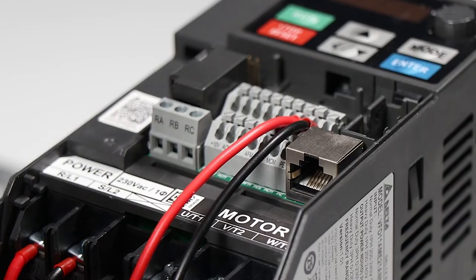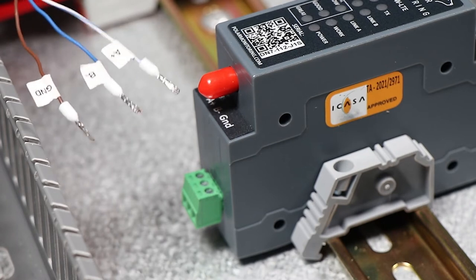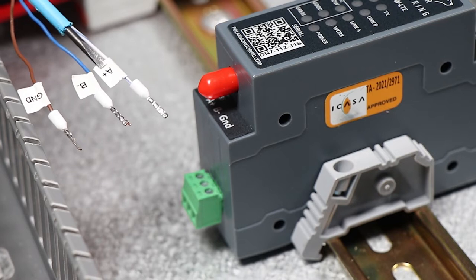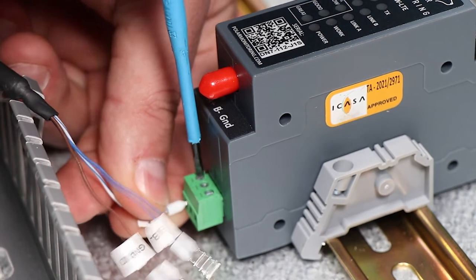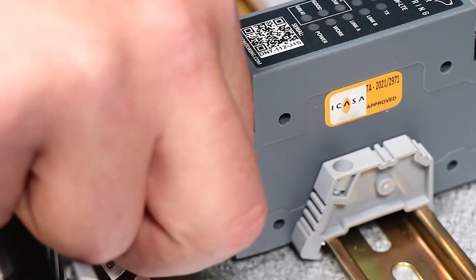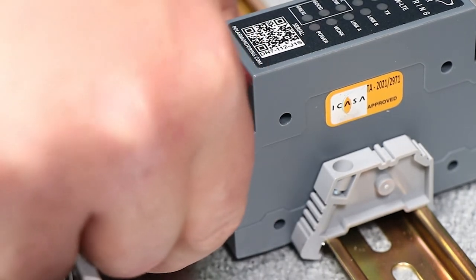We'll start by plugging in the RJ45 cable into the port. Next, we're going to wire the breakouts into the Polar Monitoring Gateway. These are broken out into A positive, B negative, and ground. We wire A positive into the gateway A positive, B negative into the gateway B negative, and ground into the Modbus ground.